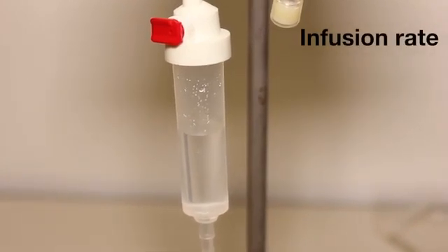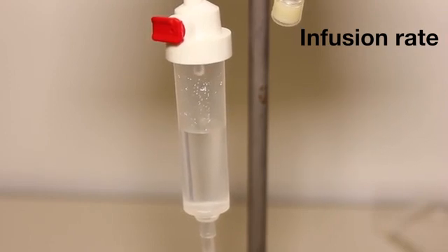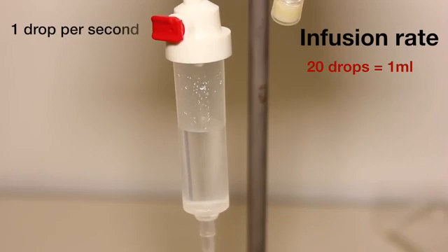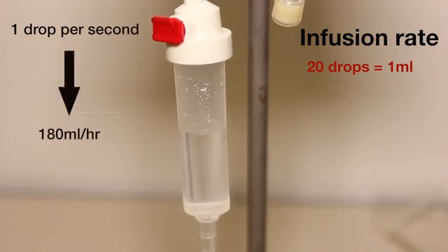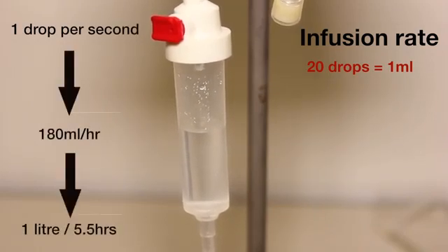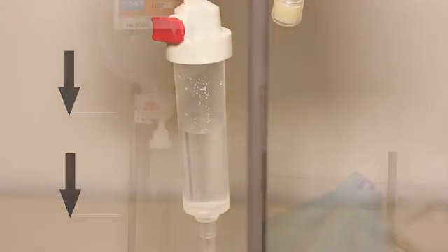This can be done by passing the tubing through a pump and setting the rate in millilitres per hour. Alternatively, you can set an approximate rate by adjusting the valve on the giving set to give an appropriate drip rate. The drops produced by the giving set shown here correspond to 1/20th of a millilitre, i.e. 20 drops make 1 millilitre. So in this case, a drip rate of 1 drop per second corresponds to 180 millilitres per hour, or a 1 litre bag delivered over about 5.5 hours.